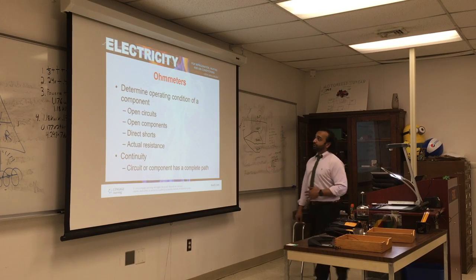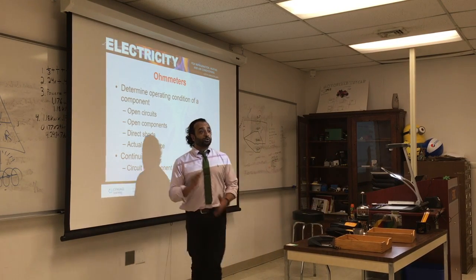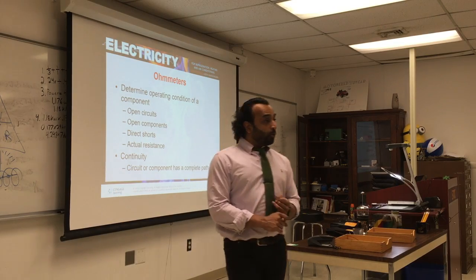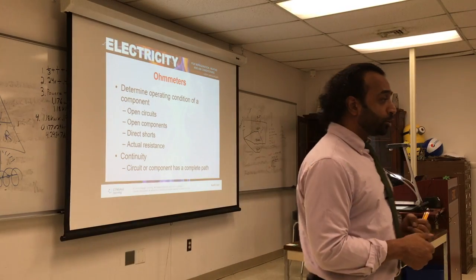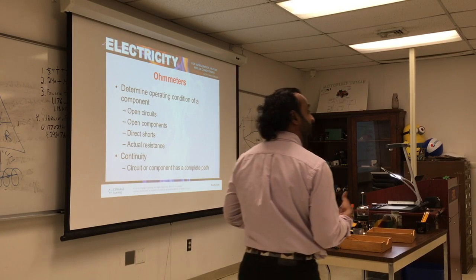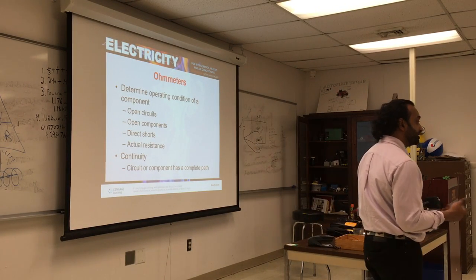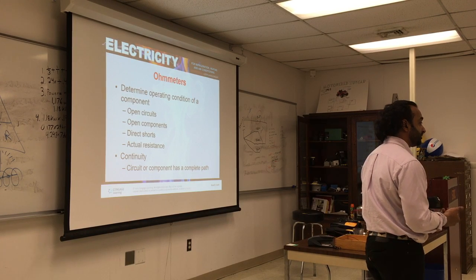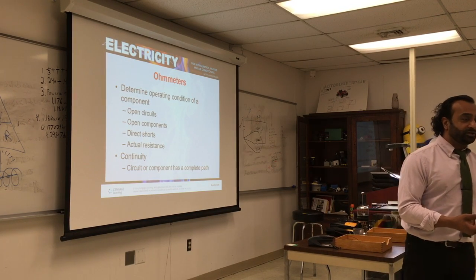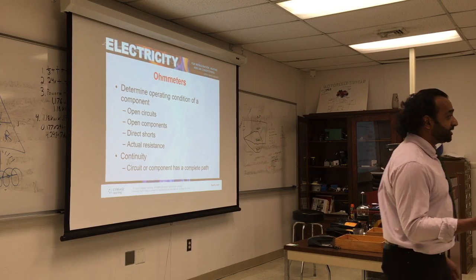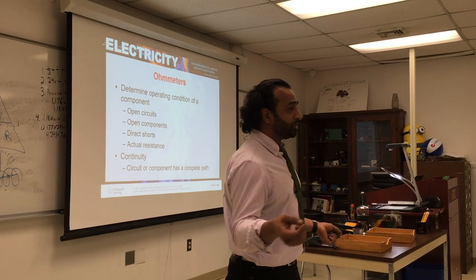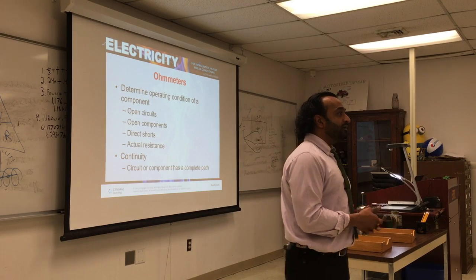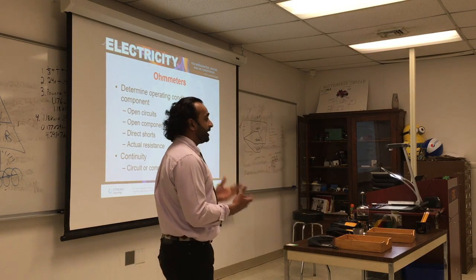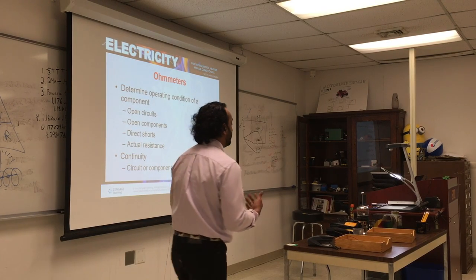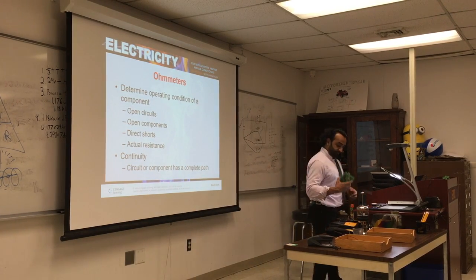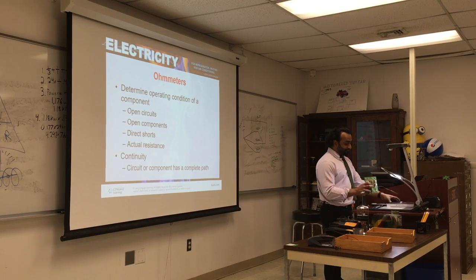Ohmmeter, they measure—it's good to measure components. We will use that a lot to measure motor windings, to measure the transformer, as I told you, compare resistance with time, decrease or changes, if something inside the transformer gets shorted. So it's very important to know how to measure resistance. Now, continuity only tells you if the wire is continuous or not, but does not give you actual resistance. So if the resistance changes, that can indicate something is malfunctioning. For example... other examples.